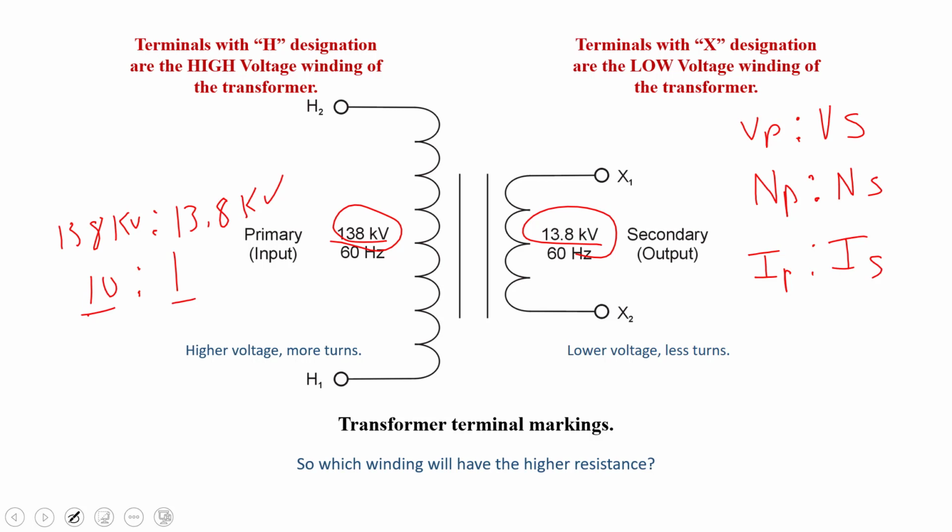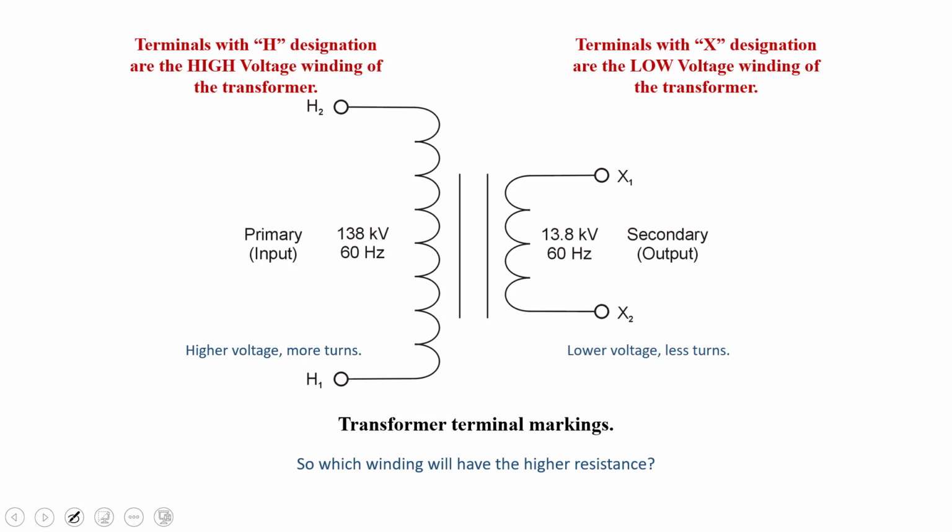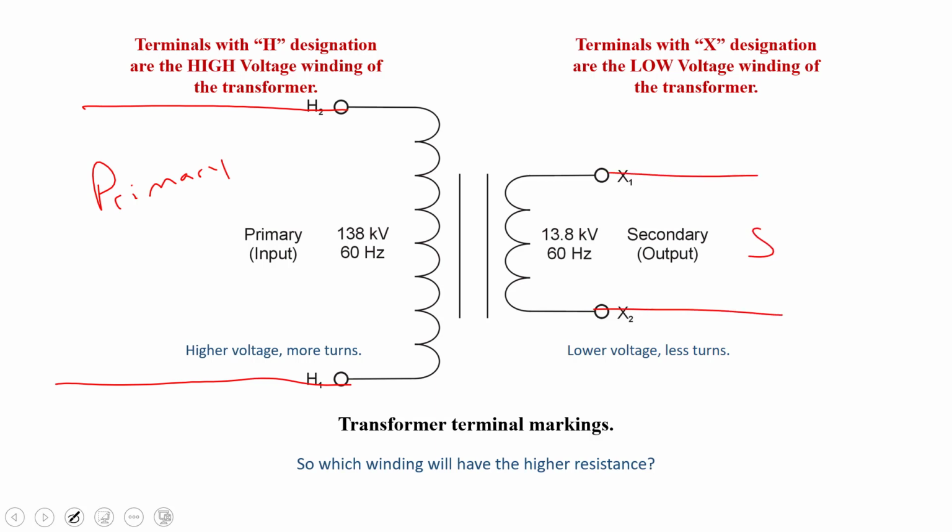All right, let's go on. We'll keep working with this. One other thing I want to talk about on this slide is that if the line comes in from the supply into this transformer, we would call this the primary. And this would be called the secondary. And so this would go out to our loads. Probably it would go to some sort of an overcurrent device, and from there probably feed a panel of some kind, and that's where our loads would be connected up. So we'd further reduce it down, smaller overcurrents to individual branch circuits.